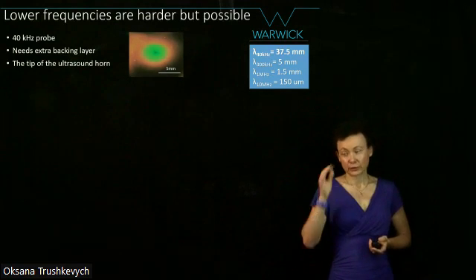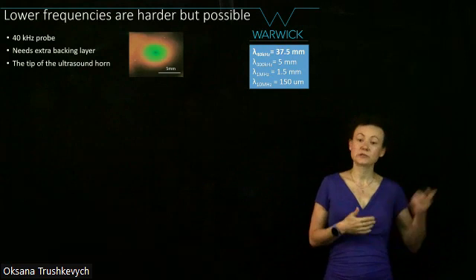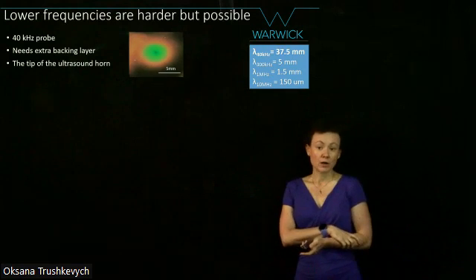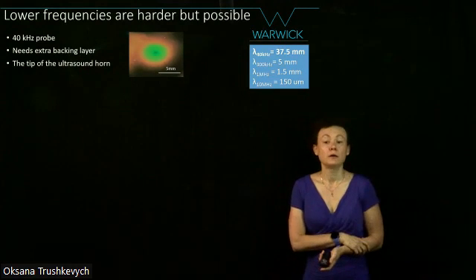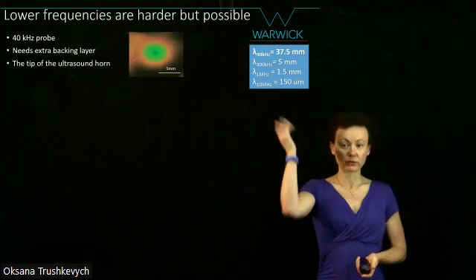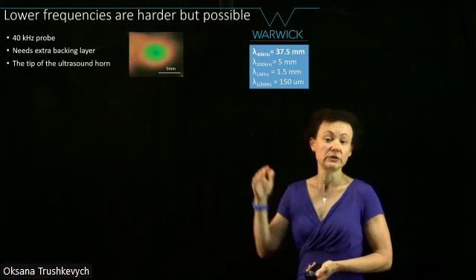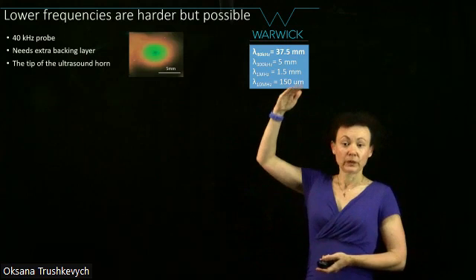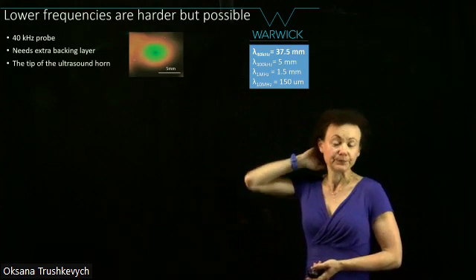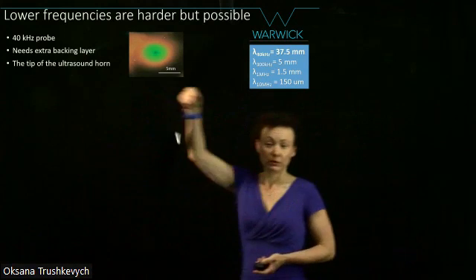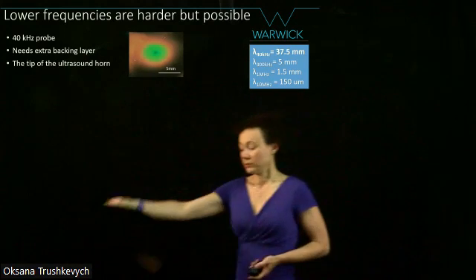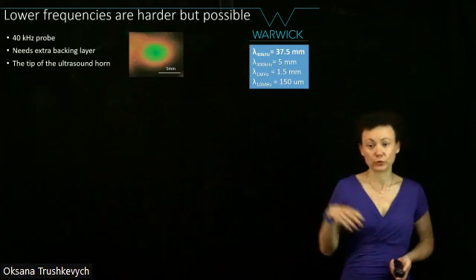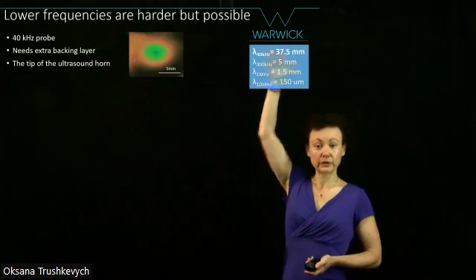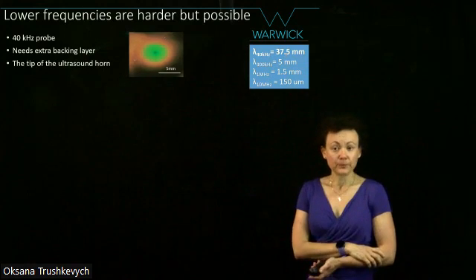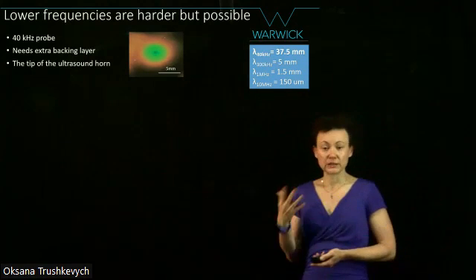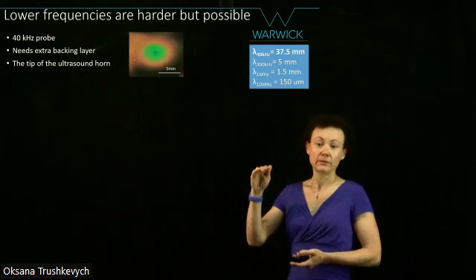I was talking about higher frequencies, 300 kilohertz and up, but what happens at lower frequencies? They're harder. They're harder because if you think about the wavelength of ultrasound that you need to absorb, it's okay-ish at 10 megahertz. This film is not very thick. It's just a plastic film. It's very difficult for it to absorb an acoustic wavelength of 37 millimeters. But we were able to add a bit of special backing layer and absorb that.